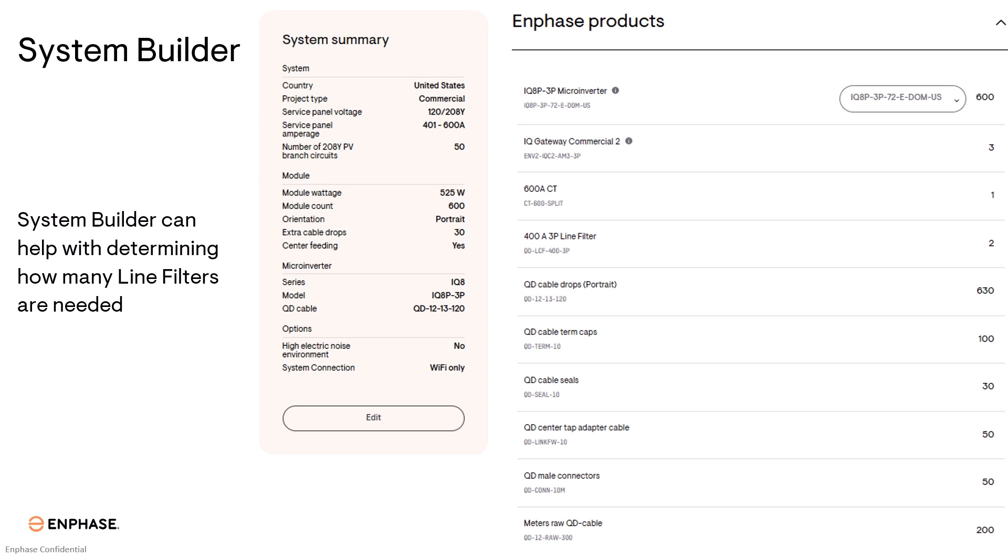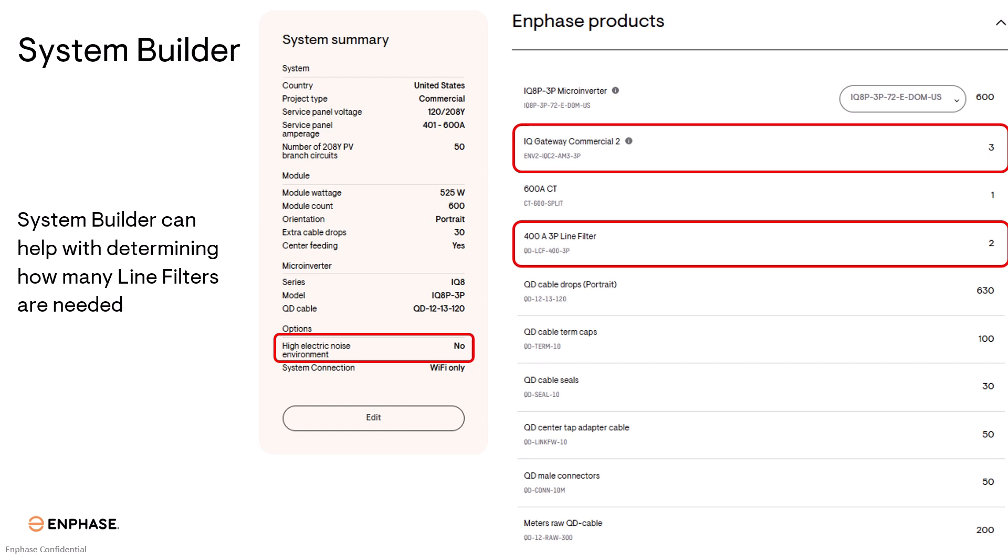If you're not sure how many line filters you may need for your project, the Enphase system builder tool can help determine how many you'll need. Once you input the required information in the system builder tool, it'll ask you if there's high electrical noise. For this example, we're going to select No. Based off of how many modules we have on this project, we will need three IQ gateway commercial twos. This means that we will need two 400 amp three phase line filters.